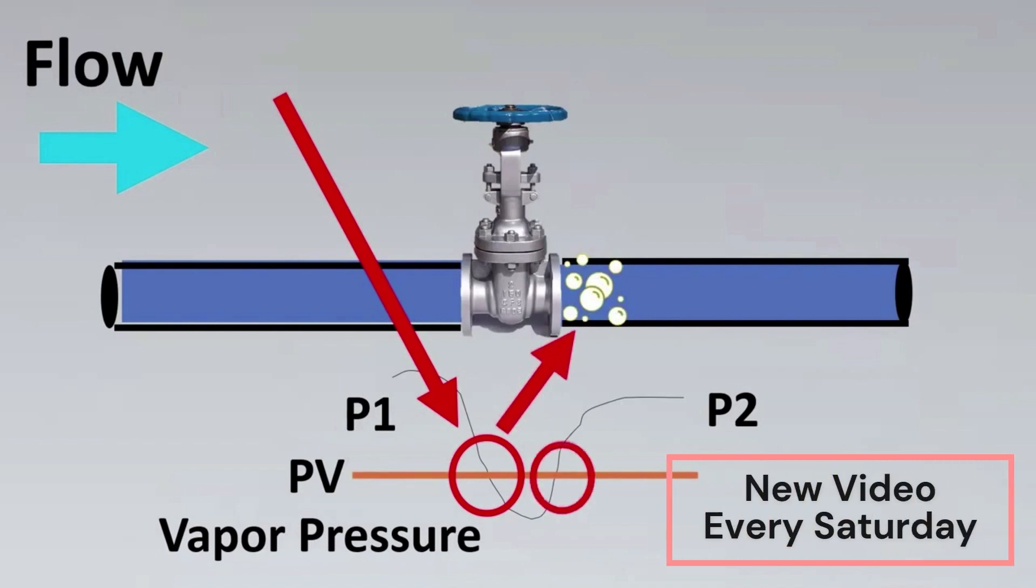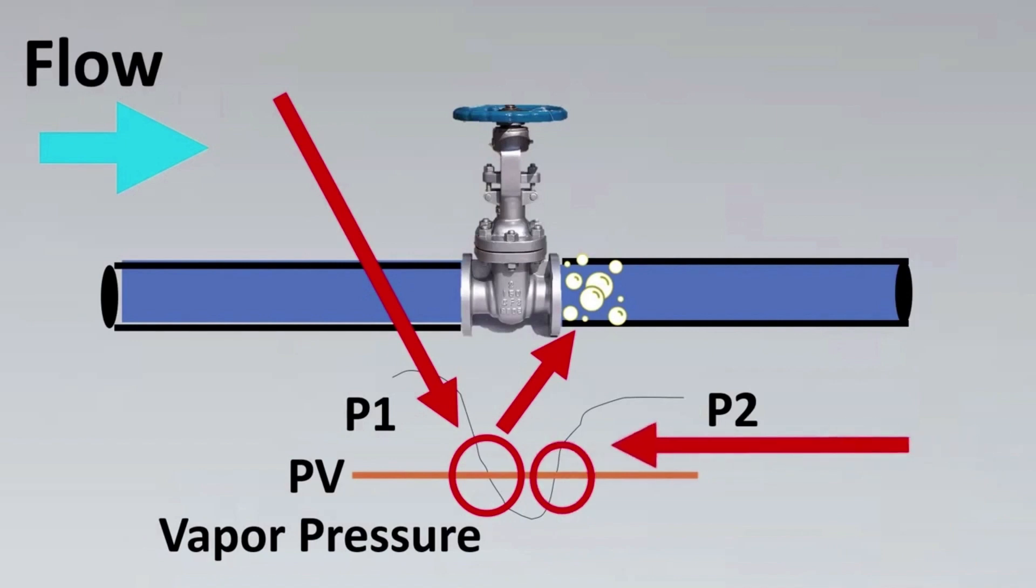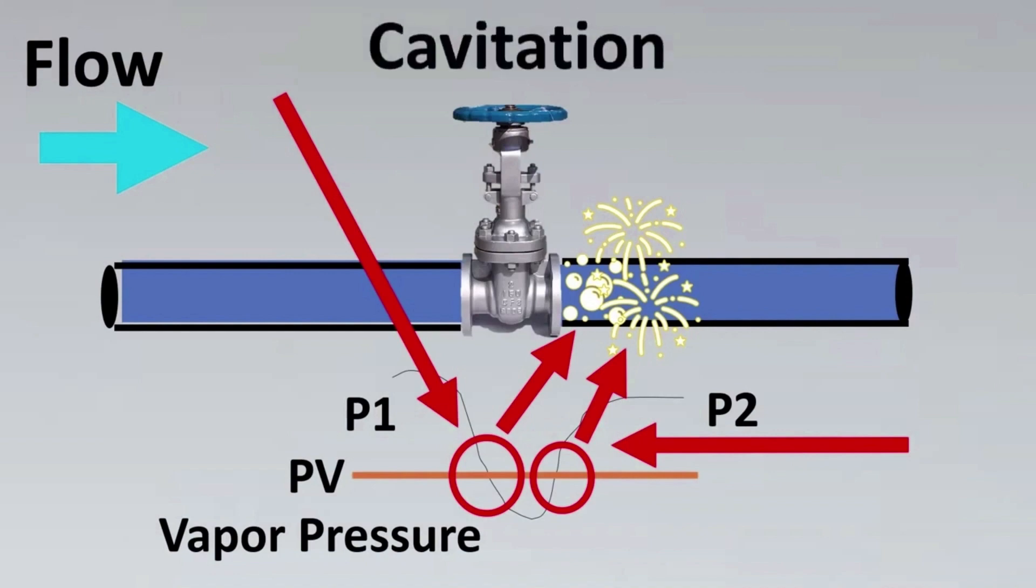At the exact opposite side, the vapor is going to turn back into liquid state. Here, what is going to happen is the bubbles are going to burst to come back to liquid state, which is called popping, which has very high velocities that can damage the valve and the piping downstream. This entire phenomenon is called cavitation.